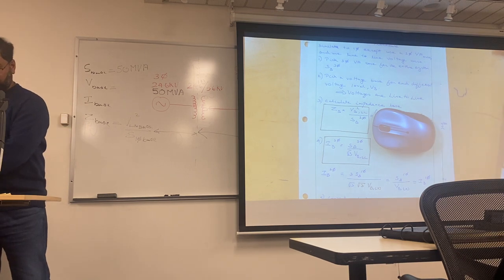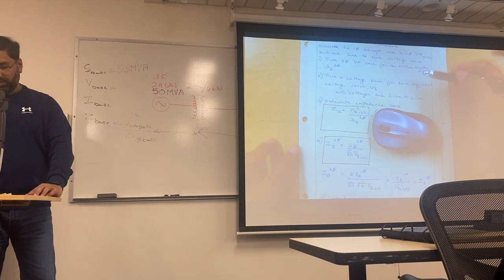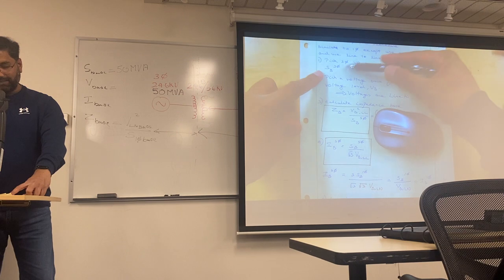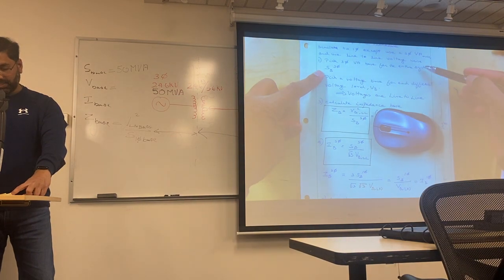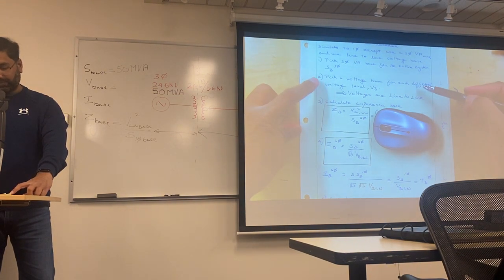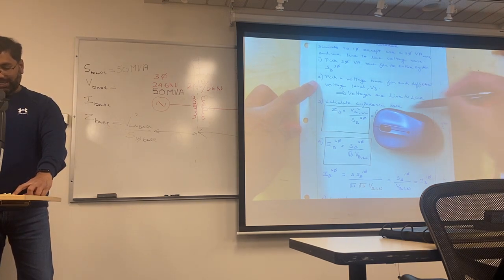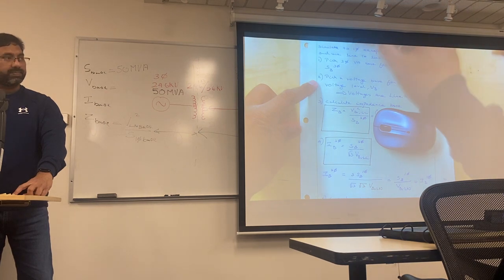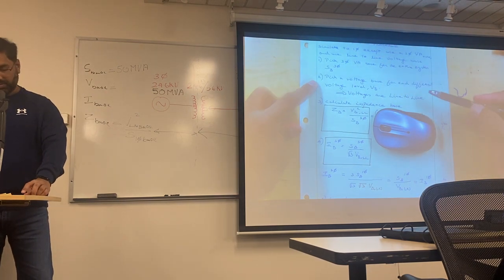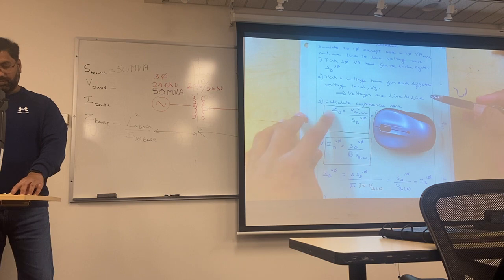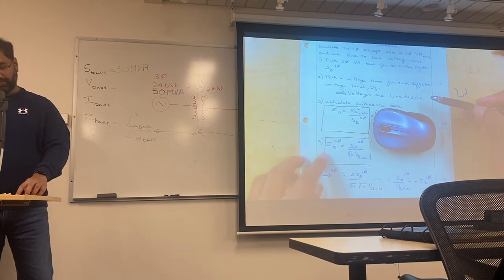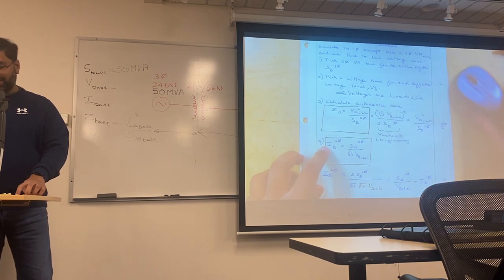You are going to pick a VA or an S3 phase base for the entire system. And then you're going to pick a voltage depending on where you are in the system. And here you're going to pick a line-to-line voltage because you're in the 3-phase system. After which you go figure out your Z base and your I base. The only thing that I was hiding here is I used a line-to-neutral voltage just to be fancy.